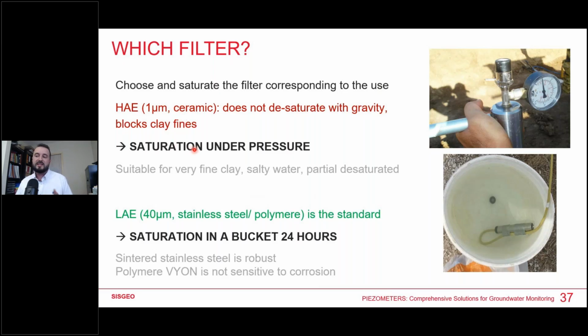The saturation of this filter is not done in just any way, so you have to use a pressure. You have to use a pump. The pump that we can provide allows you to saturate this kind of filter because it's high air entry. You need to raise the pressure above 1 megapascal in order to let the water come inside. It's suitable for very fine clay material, also for salty water, so charged with salt, and partially desaturated ground. It's very useful, for example, when you install a sensor directly inside an embankment. The embankment is not saturated at the time you are installing, so it's interesting to have a filter that does not desaturate by itself. This is why we use HAE filters for this kind of use.